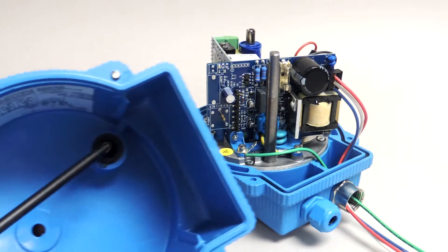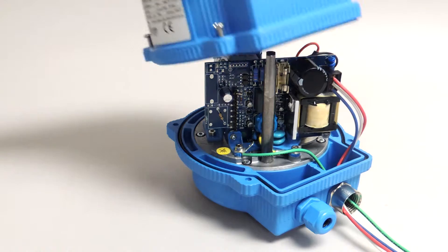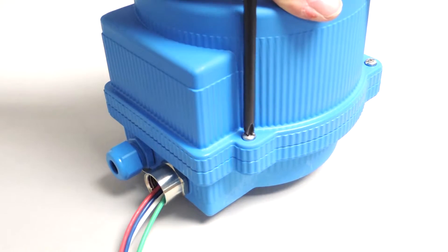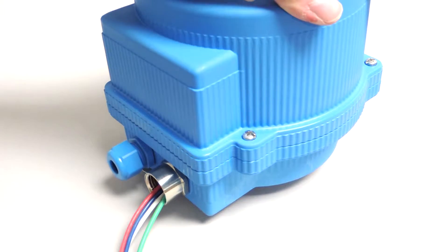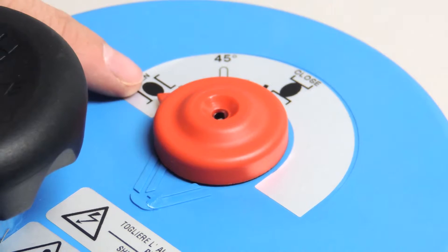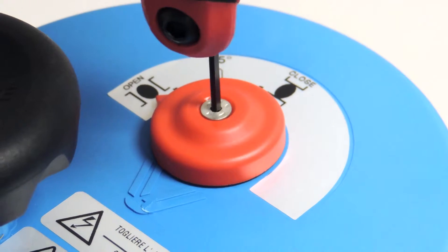Make sure that the manual shaft lines up with the hole in the outer shell and put the shell back onto the unit. Reattach the four screws. Put back the red indicator dial, making sure that it is pointing between the open and closed positions to ensure accurate readings during operation.